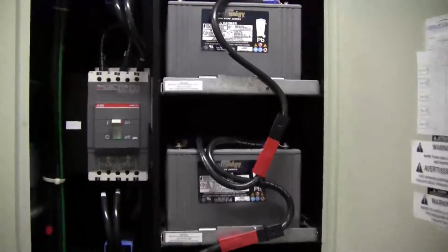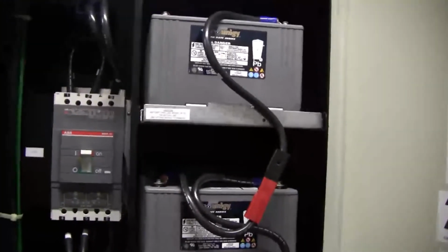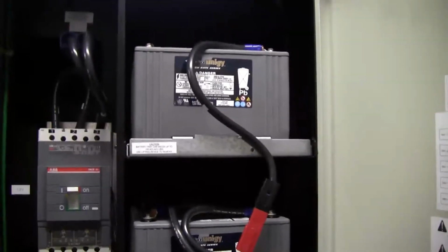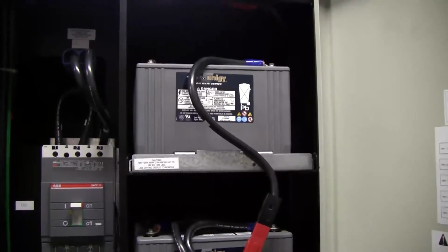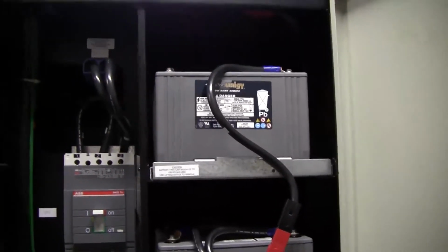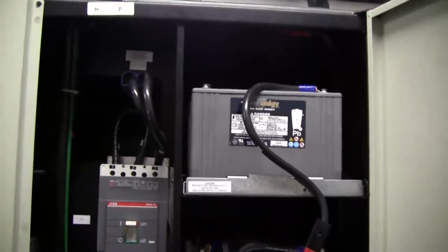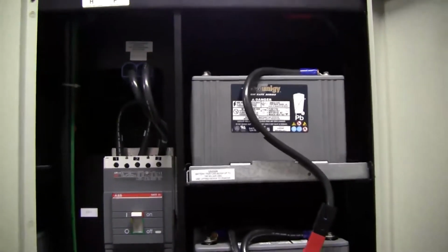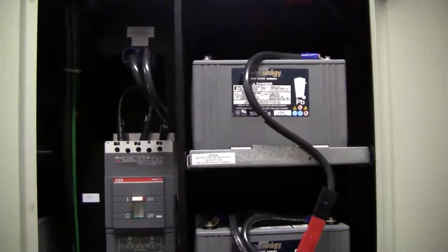These are tested every quarter, four times a year. A person comes in with a meter and tests them for quite a few things. Basically, if we have one bad cell, the whole row gets replaced. A lot of data centers will test maybe once a year, but we test every single quarter.